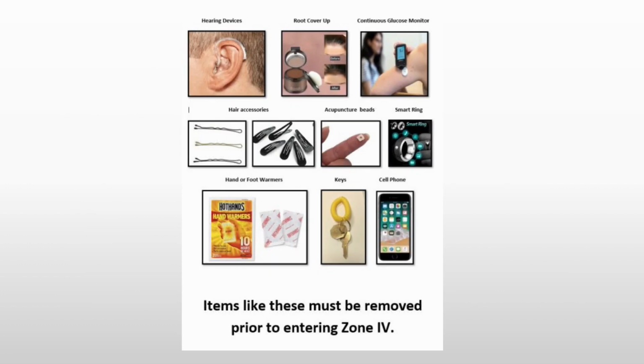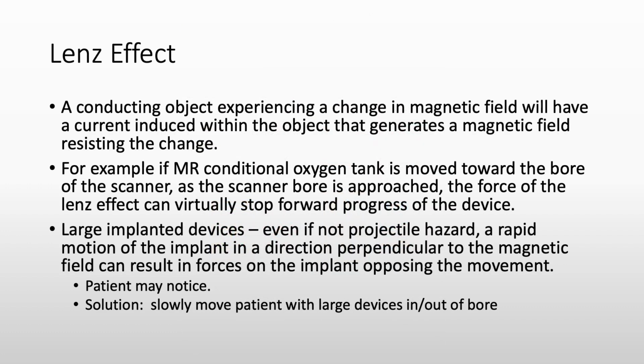A graphic like this provided to the patient is often helpful prior to their entry into Zone 4. A unique situation occurs within static magnetic fields when conducting objects are moved. The Lenz effect occurs, and it opposes the movement of the object. For example, if an MR conditional oxygen tank is moved toward the bore of the scanner, as the scanner bore is approached, the force of the Lenz effect can virtually stop forward progress of the device.